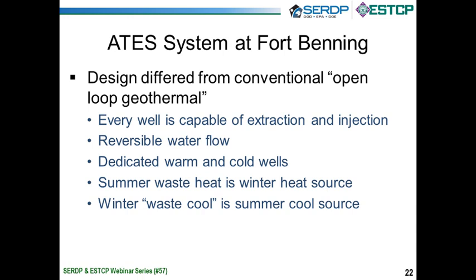Open-loop geothermal systems in general are not reversible. So you pull the water out of the ground. It's a nice heat source, heat sink. You inject it where you hope, hydrogeologically speaking, you're downstream so that it doesn't short-circuit back to the supply wells, and you throw it away. You throw away the waste heat all summer. You throw away the waste cool all winter, and you don't do these systems unless the groundwater velocities are low. Both our sites are typically below 15 feet per year of movement in the aquifer based on our measurements.